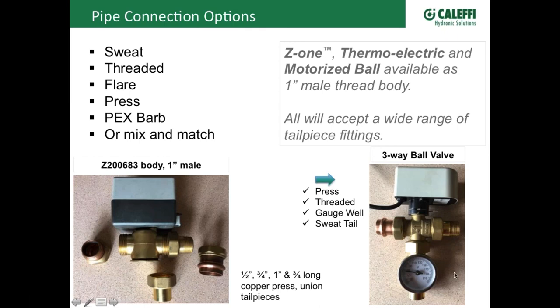Now also over here, this is kind of clever, we've got a little gauge adapter that goes on that thread also, on that 1-inch G thread. So let's say you're using this three-way valve as a mixing valve or something like that, and you want to know what the temperature is coming out of it, you can put that adapter on one of those ports, or temperature coming into it, whatever the case might be, and now you've got a little bit of an indication to adjust or balance or something like that.